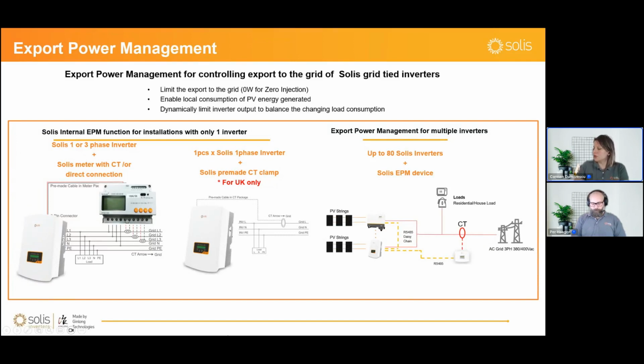And the other solution that we have is for when you have multiple inverters connected to the same grid connection point. For this case, we will need not just one meter, we will need an EPM, export power management device. This is what we call it. We have several types of EPMs, EPM single phase or three phase, depending on the type of inverters you're connecting to it.